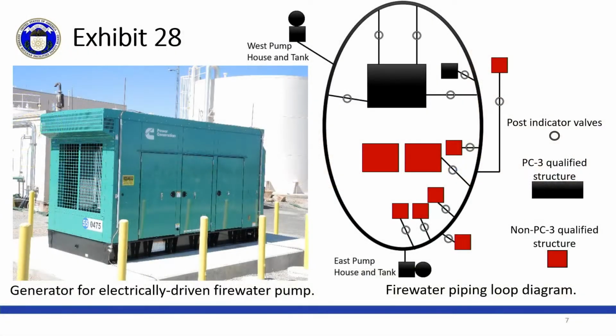I'm going to look up to make sure that that's what that shows. Yes, okay. Because these facilities all have different seismic pedigrees, we can't be assured of the whole loop's performance following the bounding seismic event. In other words, there might not be enough water for PF4 because of pipe ruptures in these other structures. So can you discuss the current schedule and any concerns with completing the work on the sprinkler piping in PF4, establishing a new fire water supply loop to separate PF4 from the non-seismically qualified buildings, and implementing these upgrades in a revised safety analysis?